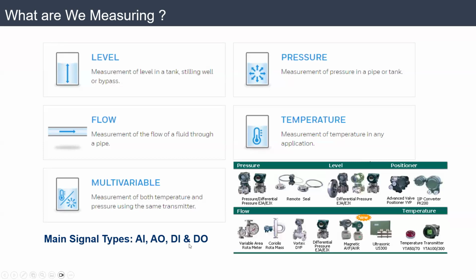For DI/DO, this is for a pulse or type of signal that is either on or off. For example, I am receiving from the pump that it's on - so I'm receiving DI. Or I am sending to the pump 'please start' by clicking on the control room monitor to the pump to start - so this start signal will go to the pump and it will be DO. Okay, I hope it's clear.